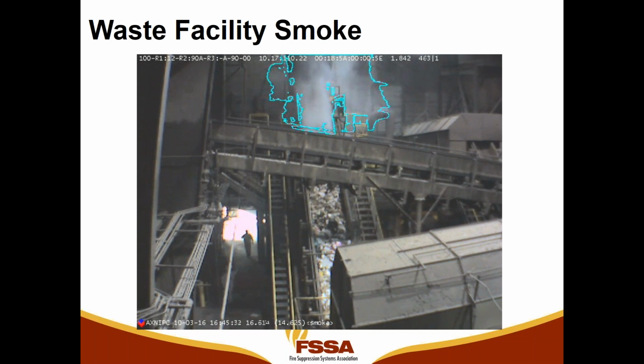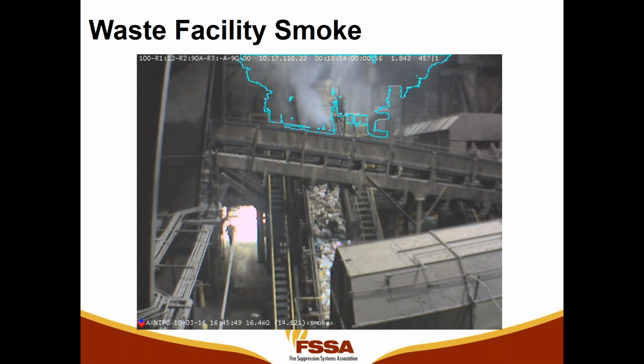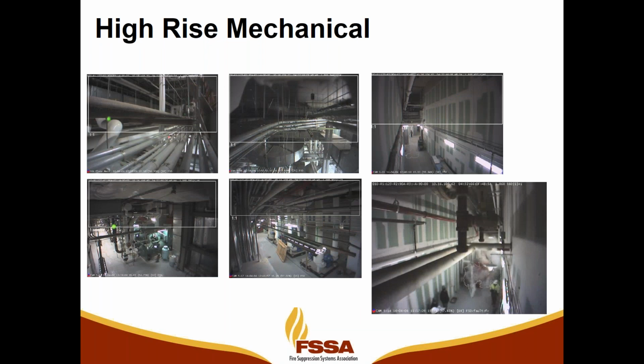Smoke detection is being used in waste facilities now that there are a lot of increased amount of fires in waste facilities due to lithium batteries. So this is an example of video analytics smoke detection being applied. High-rise mechanical equipment rooms, or any mechanical equipment rooms, are a good application for video analytics. In this image on the bottom right-hand side, that's the fire department acceptance test, the smoke emitter, the smoke rising, moving into an alarm zone.